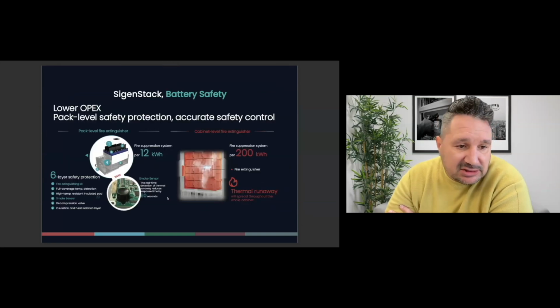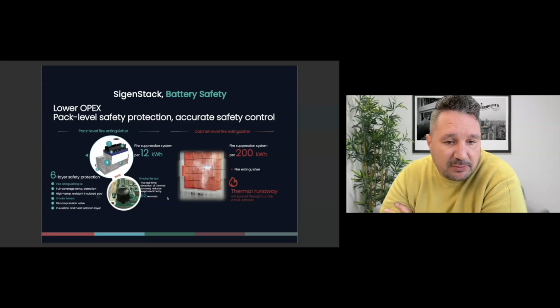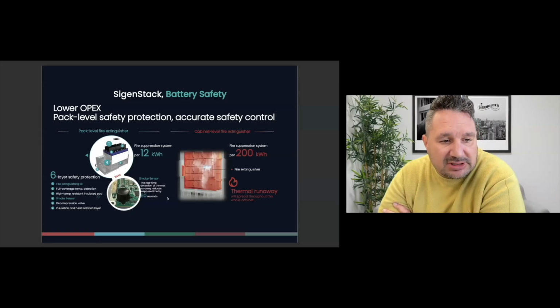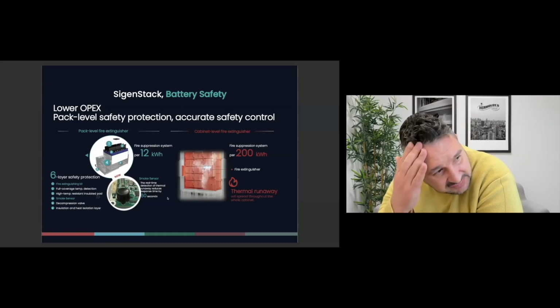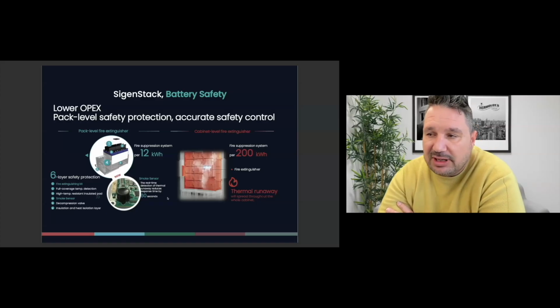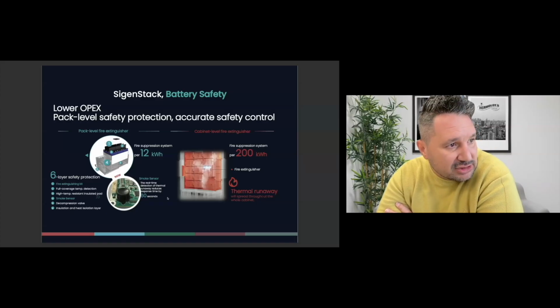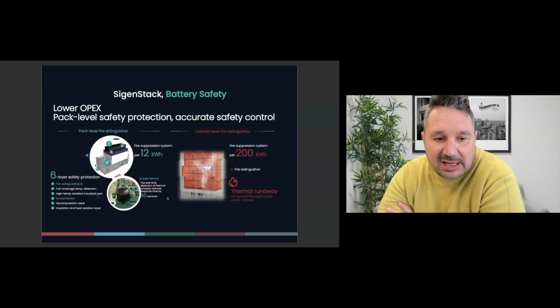The battery safety that's built into SIGEN Stack is a 6-layer protection. It covers all of the same ones from the previous gen, which is the light commercial section, but it also has a built-in smoke sensor. If you look at traditional systems, you either have battery safety protection at a pack level, which is 200 kilowatt hours, or even at a container level, which is 5 megawatt hours. With this system, you have battery safety protection per 12 kilowatt hours. This makes sure that the battery runs at the optimal safety level, and if you should have any issues, that is always isolated to just one component and not the entire system.